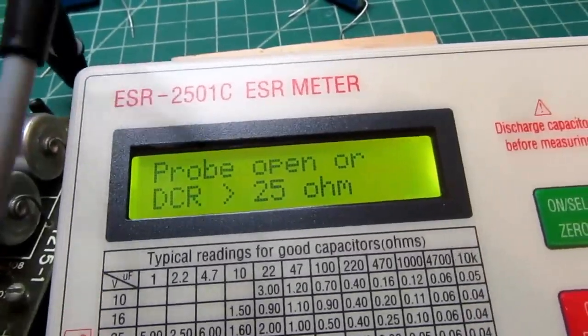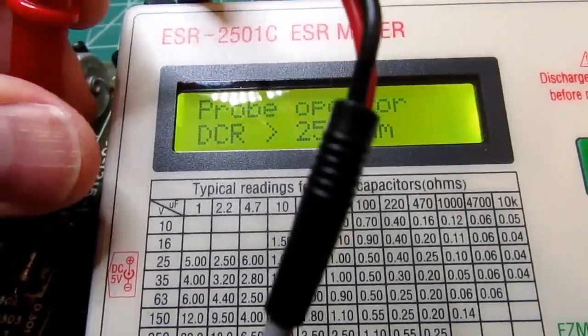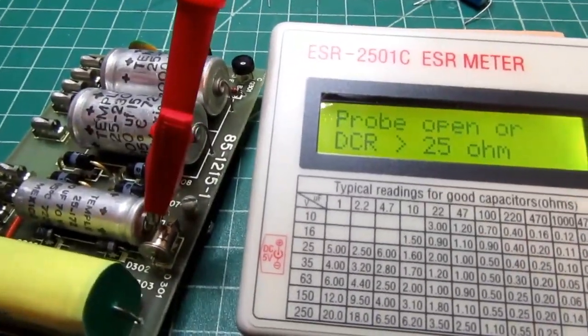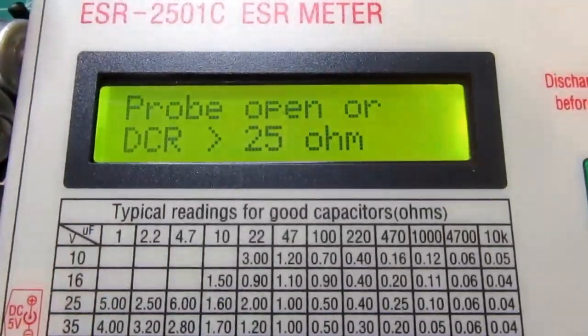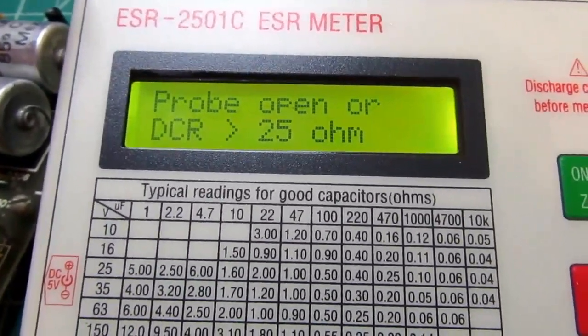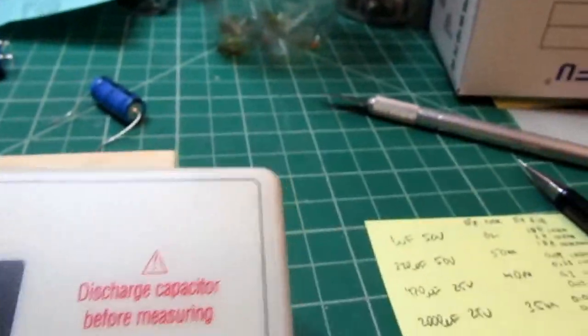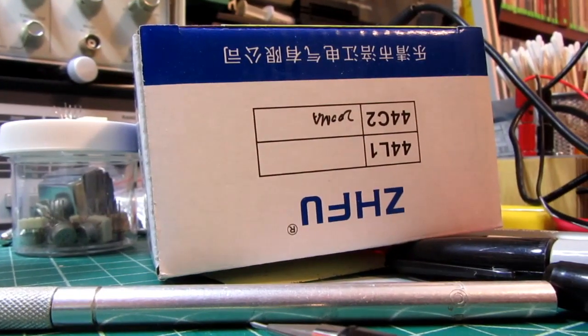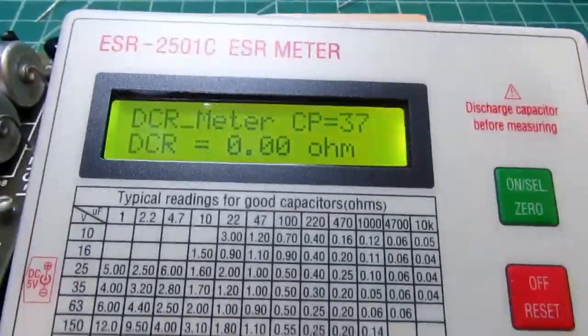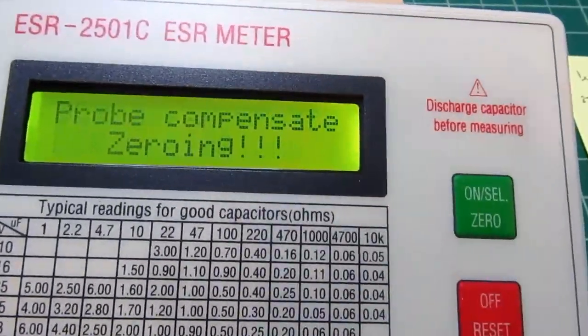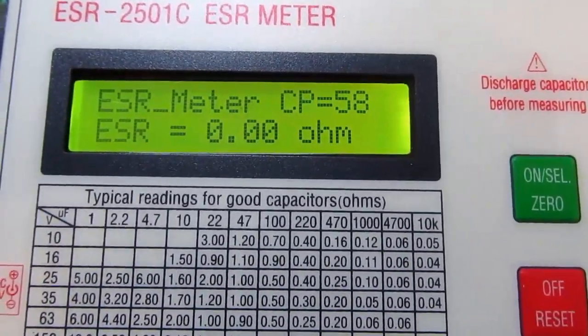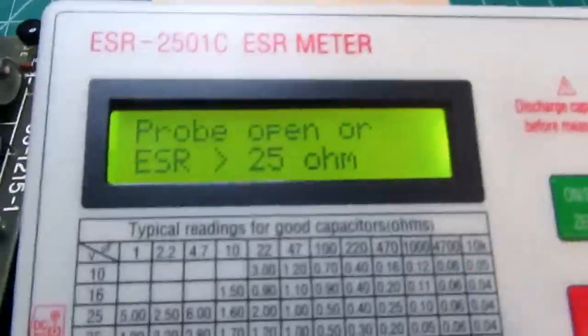Let's try this other capacitor. It's really hard to get onto this one with these big test clips. Okay, it's showing greater than 25 ohms, so that's good. Now let's short the test leads together, and I'll put the meter back into ESR mode. Let it do its zeroing, and now we're back in ESR mode showing 0 ohms with the test leads shorted. Now it's showing probe open with the test leads unshorted.